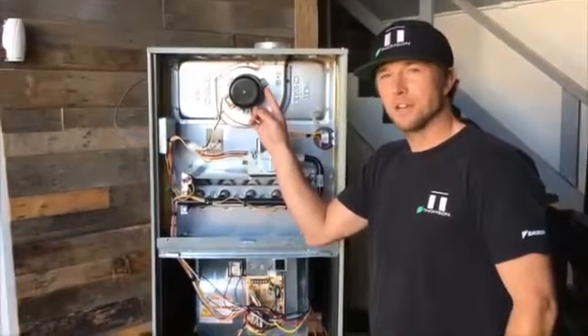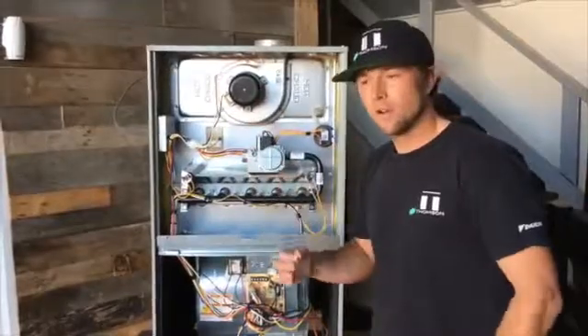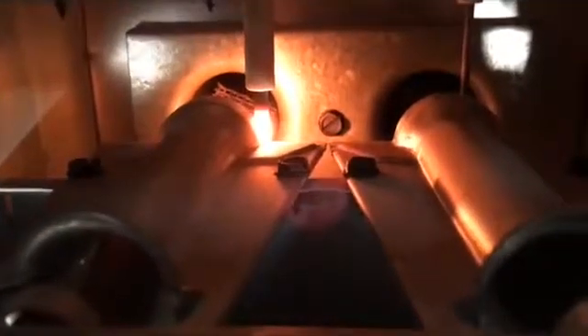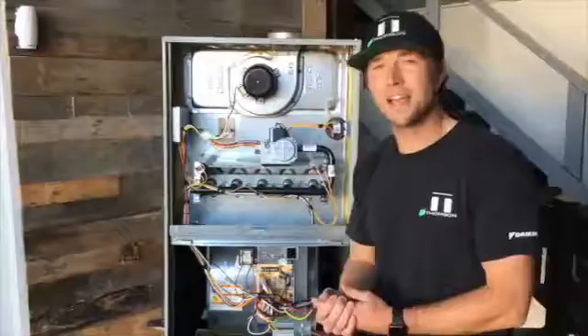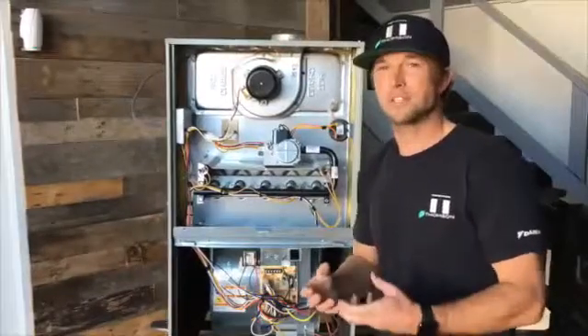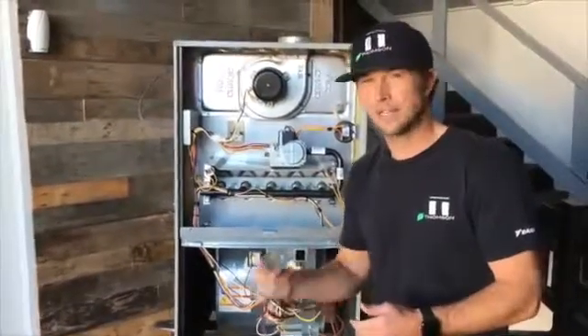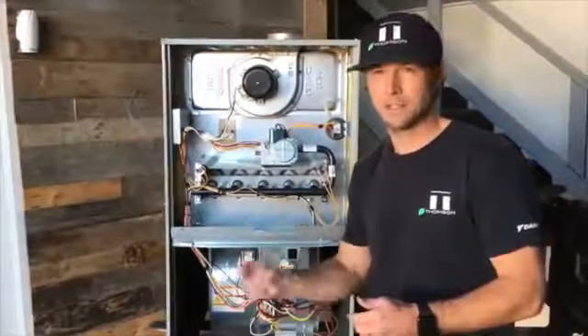After the inducer motor is turned on, we have to now create some sort of heat so we can ignite the gas. You're gonna see a little glowing in your furnace somewhere around the burner compartment — that's your hot surface igniter. On older furnaces, if your furnace is from the 80s or even the 90s, you're gonna see oftentimes a spark ignition system; you'll hear a little ticking happening every few seconds until that pilot comes on and lights.